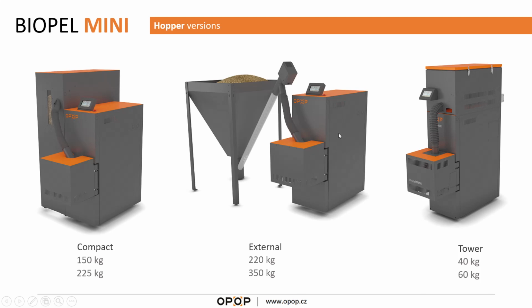Speaking of pellet hopper sizes or types, we have, as you know from before, the compact version, which is currently for 150 and 225 kilos of pellets. We have an external hopper for 220 and 350 kilos of pellets, and we have a new tower version, basically a hopper placed on top of the boiler, with sizes 40 and 60 kilograms. So basically it should last for 1 day of usage.